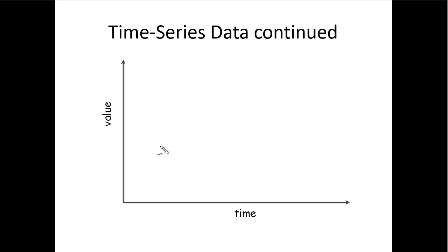So let's look at another example here. Let's look at a signal that does something like this. So what's happening here? Let's say this is a value of 1. I'm reading 1, I'm reading 1, I'm reading 1, and then something interesting happens. Or maybe this isn't 1, maybe it's 0. So maybe nothing's happening, this thing's off for a year, and then somebody turns it on. Well, if I'm taking a reading every second, I've just wasted a ton of database space, right? Because I've just got these 0, 0, 0, 0.